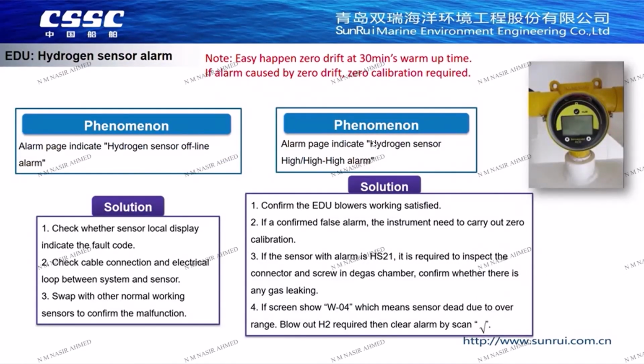It needs to be noted that zero drift of a hydrogen sensor easily occurs within half an hour after system power on. If the alarm occurs within this time, zero correction is required to recover from the alarm. The hydrogen sensor has two kinds of alarm, offline and detection high alarm. For offline alarm, first check whether there is an alarm code shown on the local screen. It gives the corresponding guidance according to the code. Secondly, check the wiring, or directly swap with another normally working sensor, to confirm whether there is a problem with the sensor itself. Most systems install two hydrogen sensors in EDU.